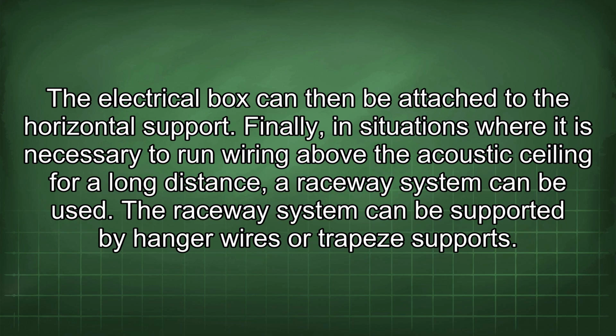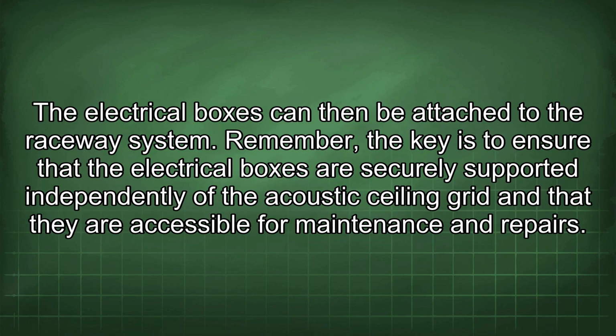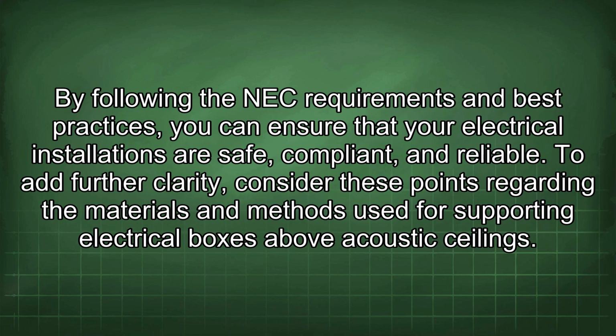Finally, in situations where it is necessary to run wiring above the acoustic ceiling for a long distance, a raceway system can be used. The raceway system can be supported by hanger wires or trapeze supports. The electrical boxes can then be attached to the raceway system. Remember, the key is to ensure that the electrical boxes are securely supported independently of the acoustic ceiling grid and that they are accessible for maintenance and repairs. By following the NEC requirements and best practices, you can ensure that your electrical installations are safe, compliant, and reliable.